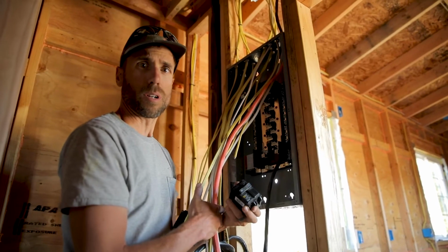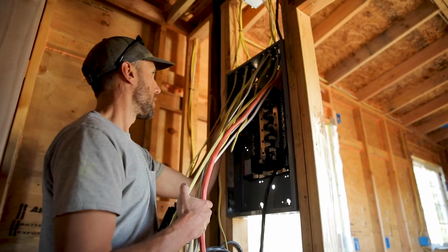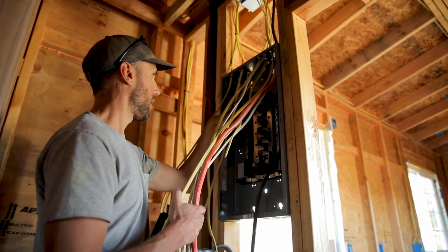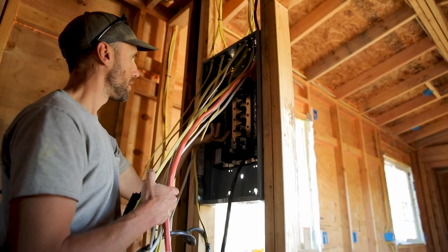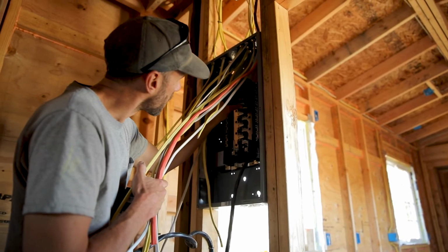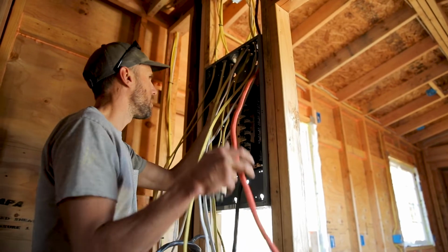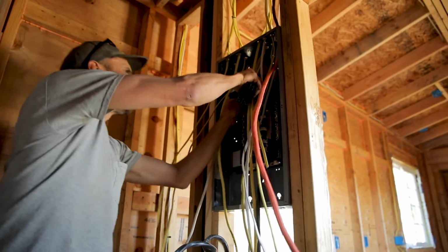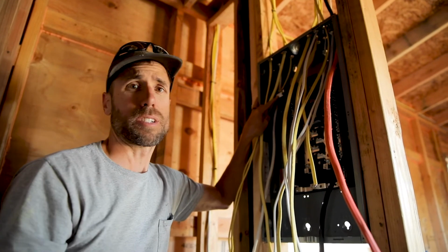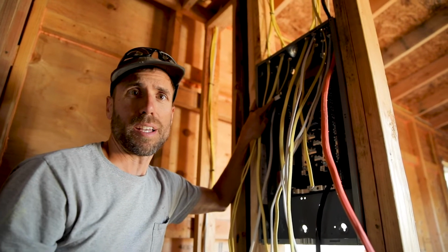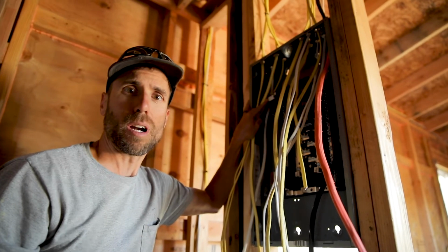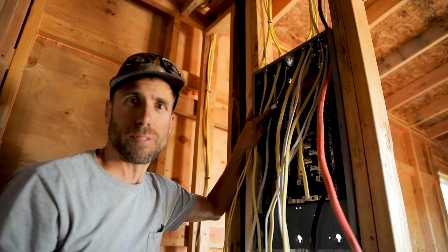You can see here for our bigger breakers, they're gonna go across this side and this side. See, they're gonna hit one of each. When you put a breaker in, you're just gonna slide this side in first, lock it in place, and then push this in. These extra long breakers here are called arc fault circuit breakers. And for building codes, they require them. It's just an extra safety feature.